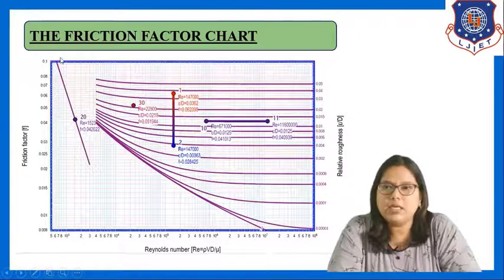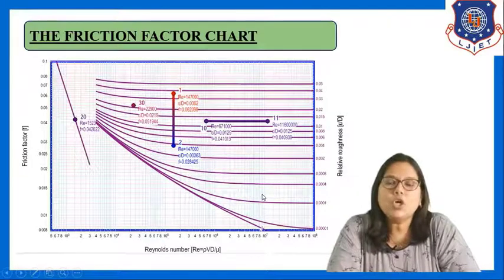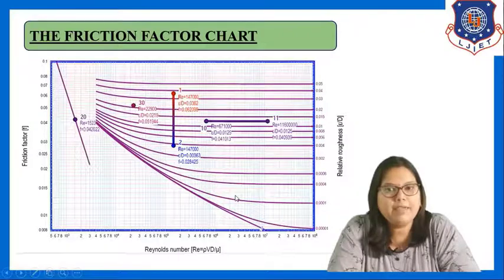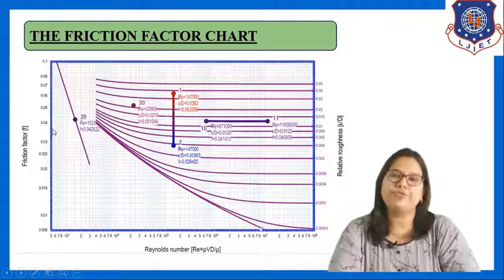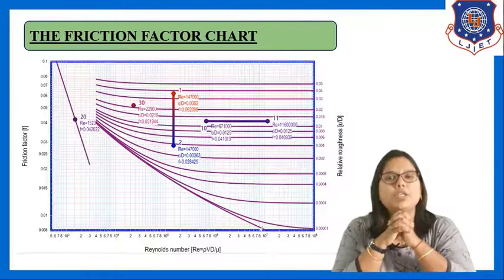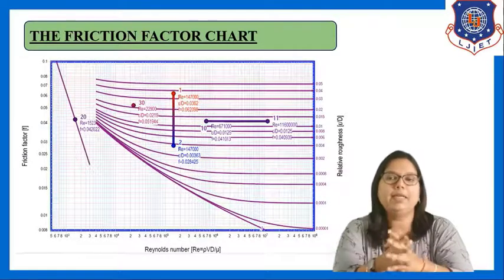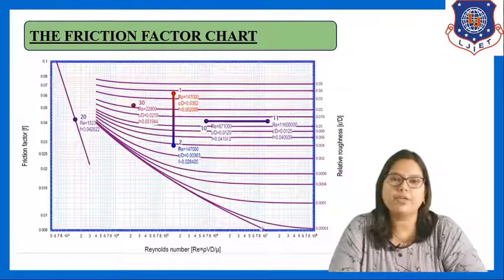There is a straight slanting line for laminar flow, and after that different curves for different k/d values. If you know the NRe value and the k/d value, you can read off the friction factor f from the chart. The friction factor chart is very important when we need to calculate friction factor graphically.